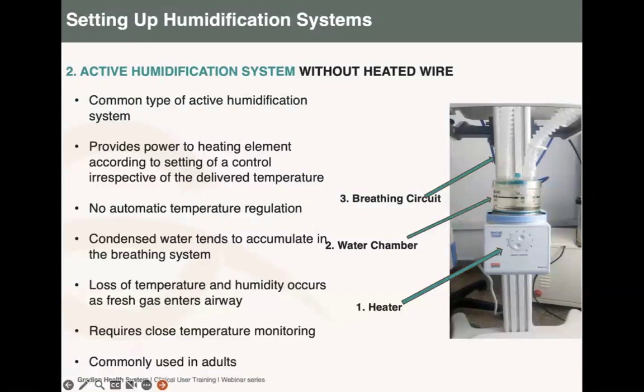You can see the heater. So you just control manually the temperature which heats the water so that you can humidify the air. So on the humidifier in which there's no heated wire, the temperature is controlled manually. The disadvantage of this is that most of the time there is a collection of water. Water is condensed and tends to accumulate in the breathing circuit. That's why, if you have seen it well on the previous picture, you can see on those breathing circuits there's some bottle which collects water. So that water will accumulate there if you are using the without heated wire type of humidifier.